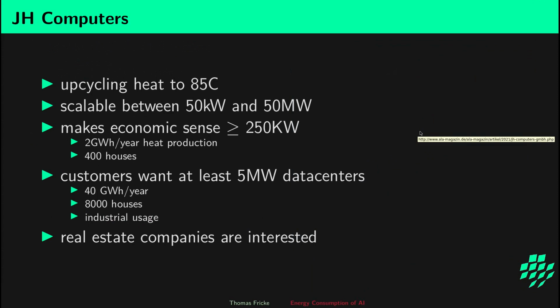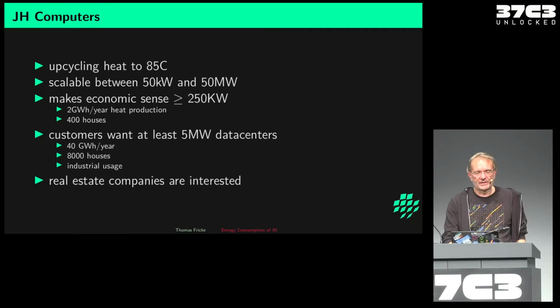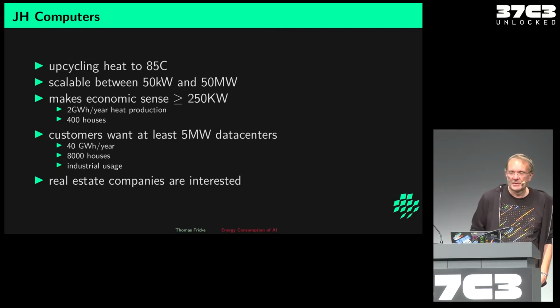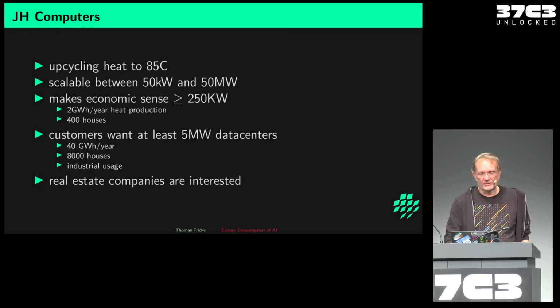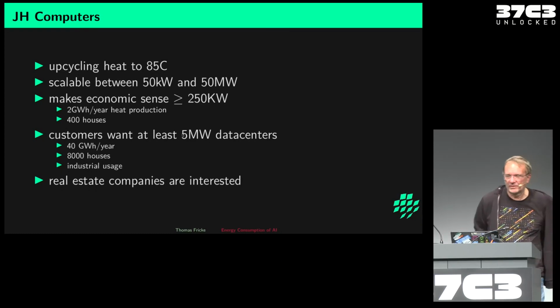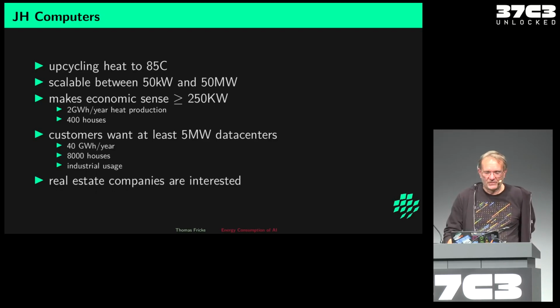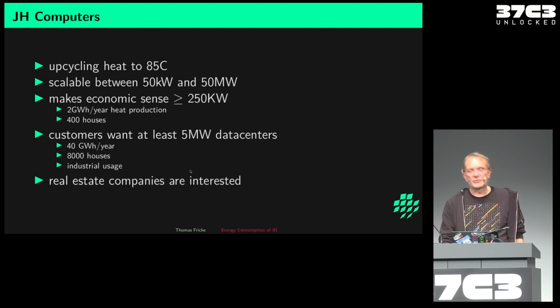I asked them what they are really doing. They are upcycling heat to 85 Celsius, and it's scalable between 50 kilowatt and 50 megawatt. It makes economic sense from 250 kilowatt. At that scale, you have 2 gigawatt hours of heat production per year, and you can heat 400 houses. But customers normally want at least 5 megawatt data centers, which means 40 gigawatt hours and 8,000 houses. So it can also be used for industrial usage. This means the first real estate companies are interested, because this can significantly lower your heating costs.